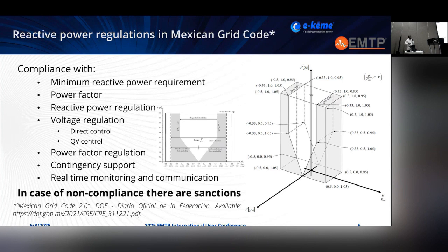To set context in the power regulation in the Mexican grid code, it's important to note that compliance must be met by the generation facilities. In this case, we're focusing on the synchronous type of machines or the synchronous type of generation plants, and they must meet certain requirements. One of them is the power factor regulation, reactive power regulation. They must meet voltage regulation at the point of interconnection, either from direct control or QV control. They must also support contingency events and real-time monitoring and communication. So compliance is not optional. There may be fines and sanctions to the users if they don't meet these requirements in the grid code.